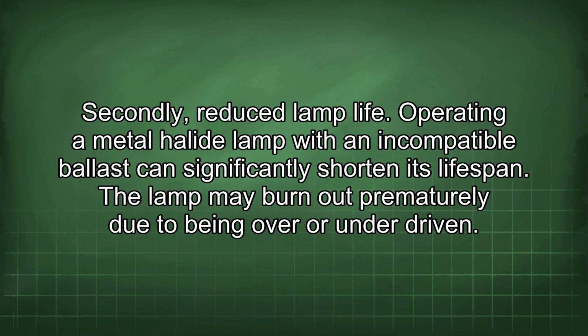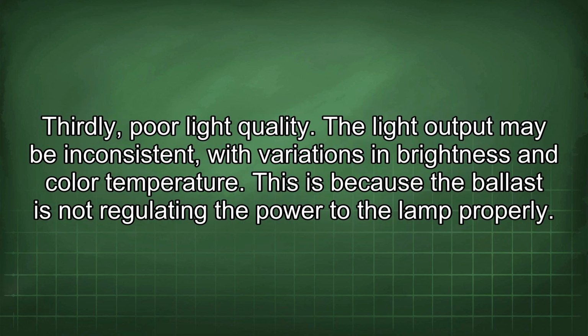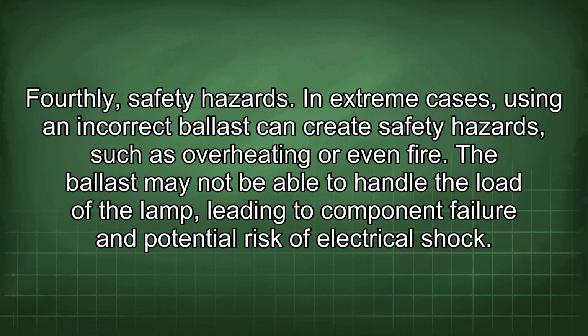Secondly, reduced lamp life. Operating a metal halide lamp with an incompatible ballast can significantly shorten its lifespan. The lamp may burn out prematurely due to being over or underdriven. Thirdly, poor light quality. The light output may be inconsistent, with variations in brightness and color temperature. This is because the ballast is not regulating the power to the lamp properly. Fourthly, safety hazards. In extreme cases, using an incorrect ballast can create safety hazards such as overheating or even fire.